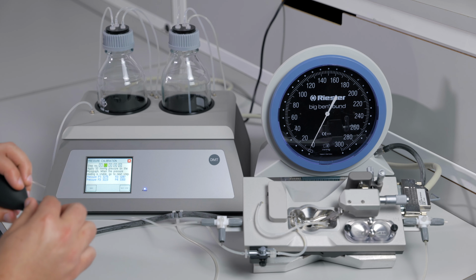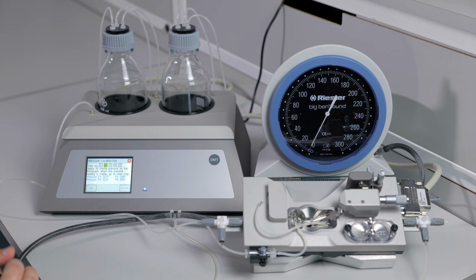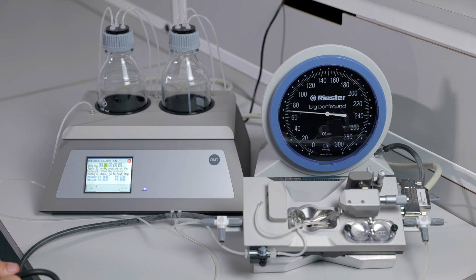Step 2 asks us to apply 50 millimeters of mercury of pressure using the Big Ben manometer. If pressure is not holding when you add from the Big Ben manometer, you have a leak somewhere. You should check the P2 bottle cap, the bleed valves on the pressure wells on the chamber, or the three-way valves. You should see all of the numbers go up similarly. They do not have to be the exact same. Once you have seen them all go up, press Next Step.